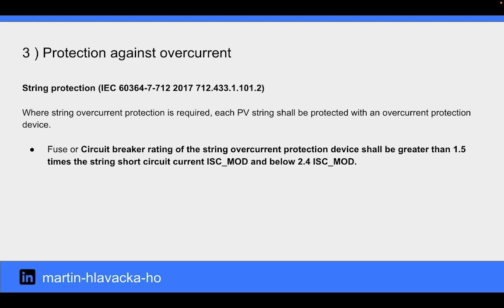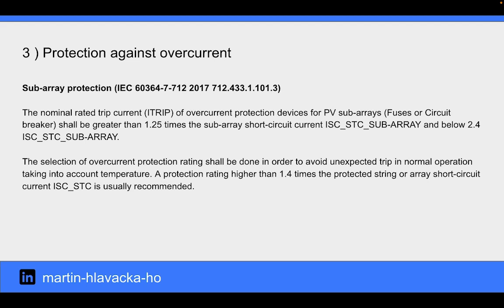Where string overcurrent protection is required, each PV string should be protected with an overcurrent protection device. The nominal overcurrent protection rating of the string overcurrent protection device should be greater than 1.5 times the string short circuit current and below 2.4 times. The nominal rated trip current of overcurrent protection devices for PV sub-arrays should be greater than 1.25 times the sub-array short circuit current and below 2.4 times.